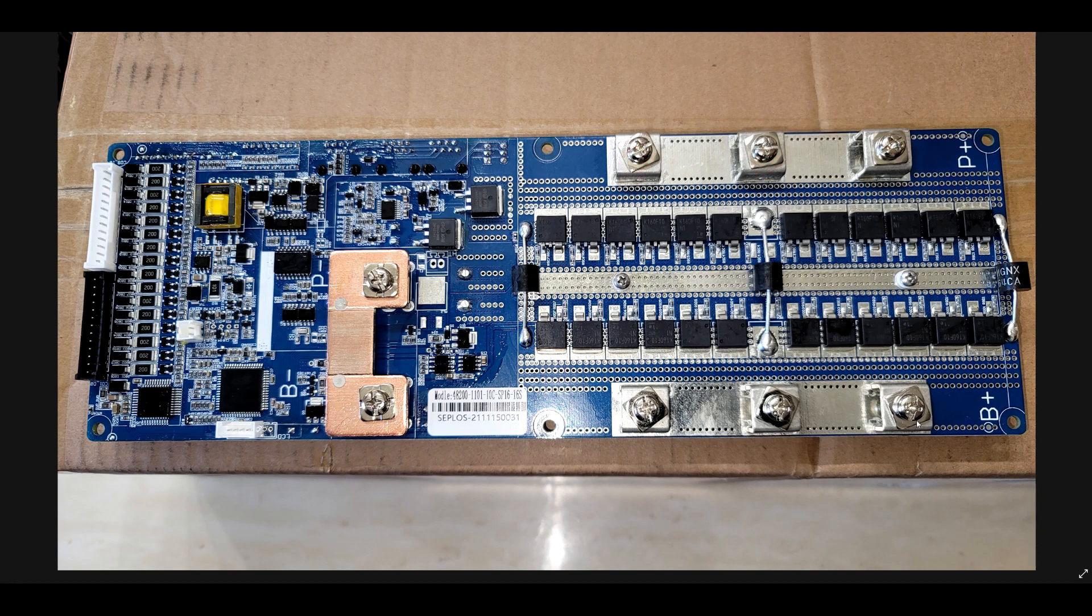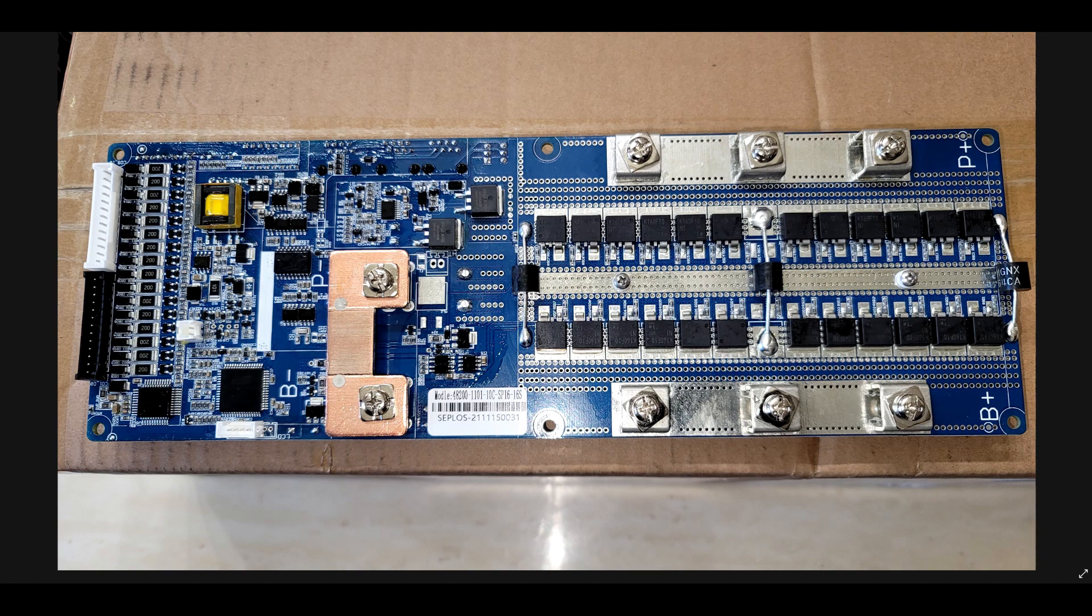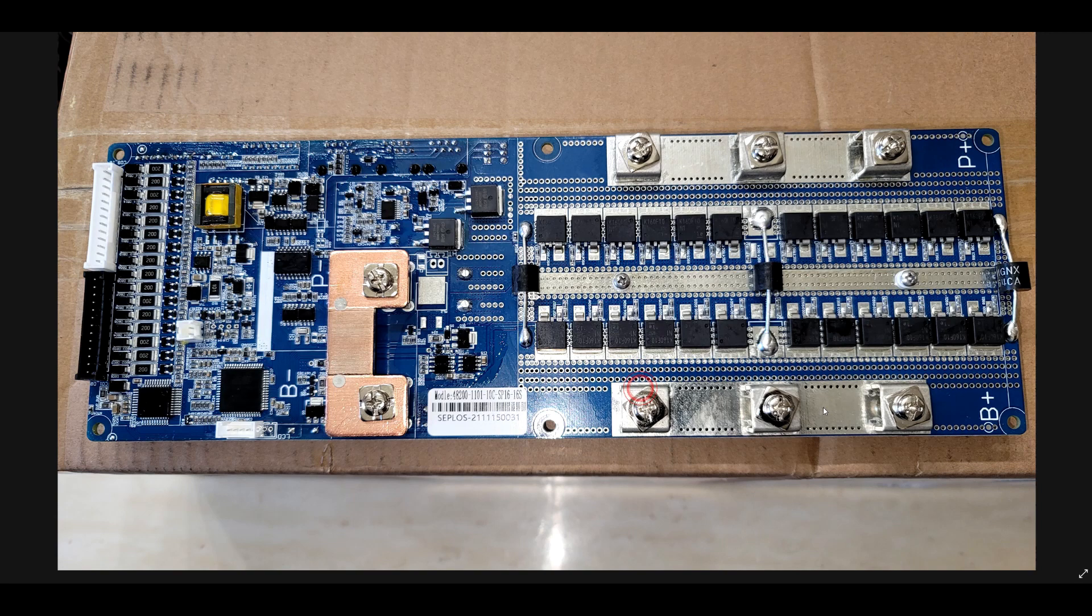The reason this is done this way is to spread current around. You should not bring just one cable over here in the middle and shove all the current across this connection expecting it to spread. They have it this way so current spread can occur right at the point of connection where the cable or bus bar comes in.